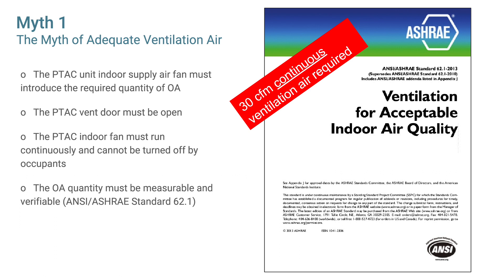Most building codes reference ANSI ASHRAE Standard 62.1 for required ventilation rates, which usually requires a minimum of 30 cubic feet per minute of continuous ventilation air. With the absence of a dedicated outside air ventilation system, the PTAC unit must be relied on to provide proper introduction of fresh air.